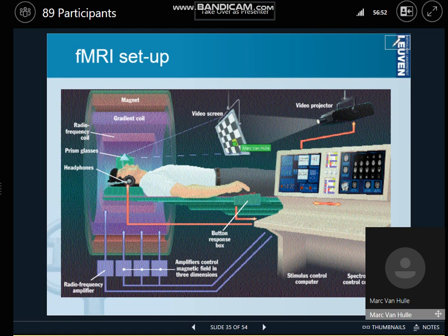And of course, in the past, people were using CRTs. You can't use a CRT. The image will completely be corrupted because of the magnetic field that is exiting the coil. Also, metallic components in the vicinity will be drawn into the coil. So it's not an easy setup. And usually you do it with a video projector so that you can keep distance, and the image is being projected onto a screen. So it is a lot of precaution there.